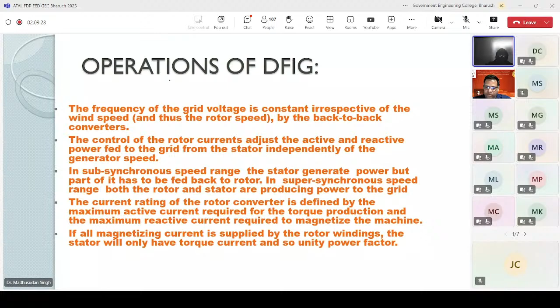Magnetizing current is supplied by the rotor winding because you see in DFIG we are not using any capacitor anywhere. Where in SCIG you saw there we were using some capacitor banks to provide the reactive power magnetizing current to those machines. So in DFIG, the magnetizing current is supplied by the rotor winding itself. Stator will only have torque current component and hence it is able to ensure a unity power factor operation at the PCC, the point of common coupling. So that's the major benefit, that with the rotor current only you can control the reactive power, magnetizing power requirement of the generator.